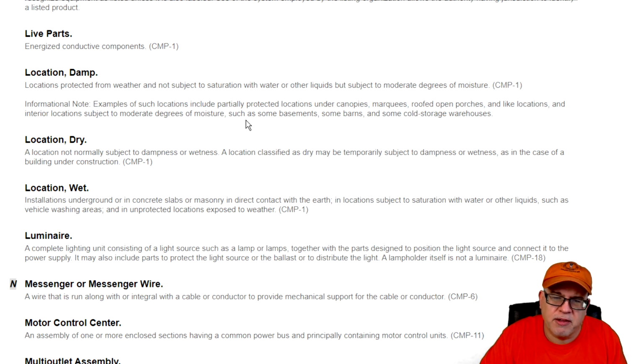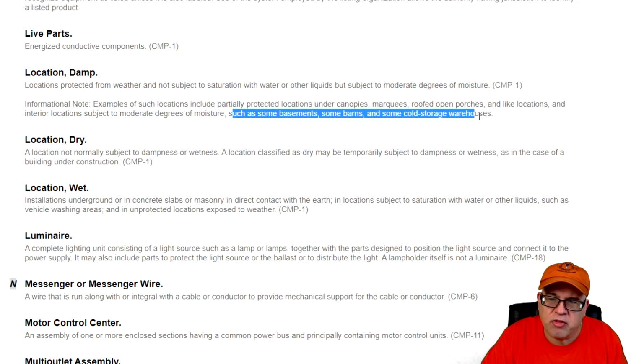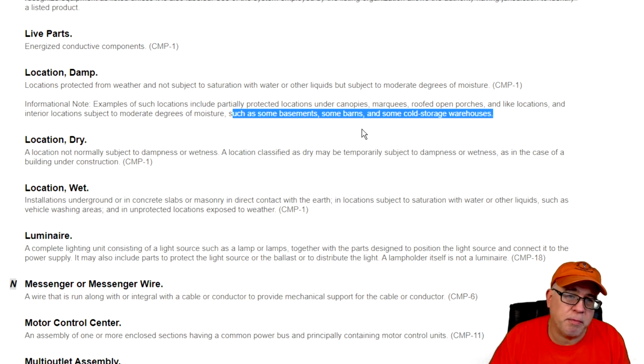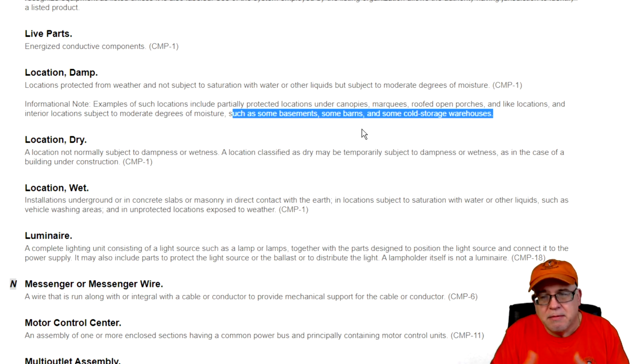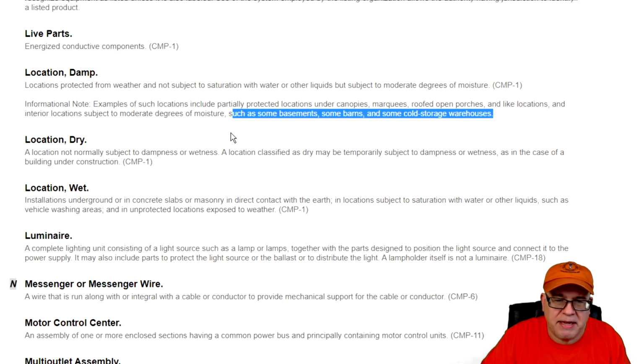Just don't fall for this, such as it says some basements, some barns, some cold storage. Just because it doesn't say crawl space doesn't mean that if I get into a crawl space and I see moisture down there, okay, puddles, pooling, I would argue that that's a damp location. If I get down there and I see it's dry as a bone and it's sealed in well, then I would argue it's a dry location. Again, the AHJ's got to make that call, but again, we're trying to make this determination.